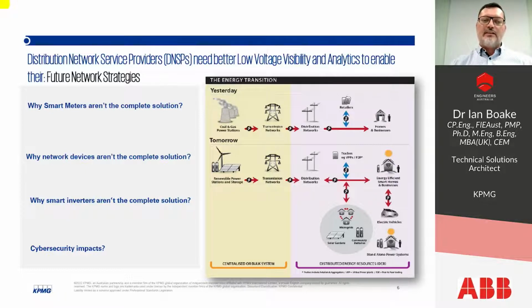So this brought about the advent of network devices, which are put basically at the distribution substation to give an early indicator, a fairly coarse measure of where the problems in terms of voltages, flows, and unbalances are experienced. But at the end of the grid, you still require smart meters to get that visibility. So state load estimation is used with smart meters as well as network devices. Some networks have between 30% smart meters, others are moving towards 40%, and I think the terminal state will probably be about 50% smart meters and therefore data penetration capabilities within probably the next 10 years. Smart inverters, as I mentioned, also communicate the voltage and certain other signals within their networks. So cyber security is obviously a very, very important thing to consider in these future scenarios.